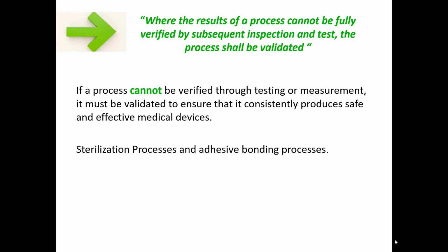So you would sterilize your device, and also, depending on the device, you might have a lot of adhesive bonding processes involved, and those are two processes that you would find in a medical device company, and they would have to be validated, because once that process is done, there is no other step in the process where you can check or inspect to make sure the sterilization process has worked or the adhesive bonding process has worked.